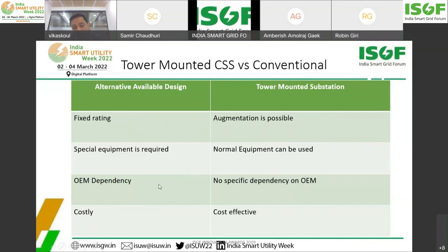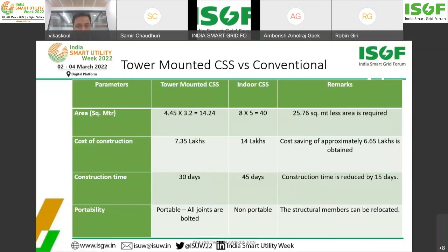In alternate designs, there is OEM dependency. In tower mounted, there is no OEM dependency. Alternate designs are very costly, and this being in-house makes it a very cost-effective solution. We have made a comparison of cost differences between conventional or alternate available substations and the tower mounted substation, and we see the cost is reduced by 50%. We are saving around 6.65 lakhs in civil cost.